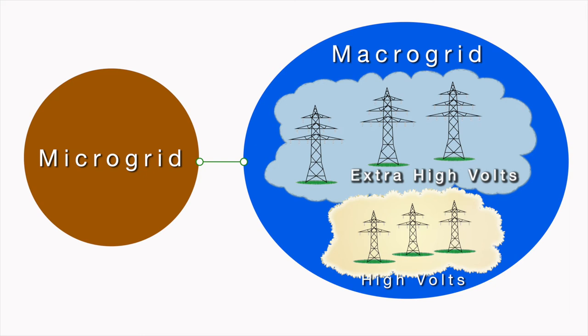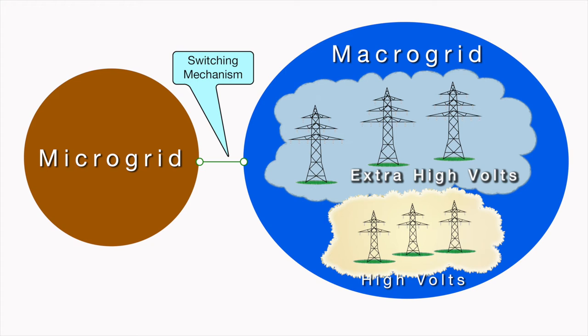Connection of the two grids is via a switching mechanism at the point of common coupling, enabling the microgrid to be switched from island mode to grid-connected mode. Having the ability to connect to the macrogrid addresses issues such as capacity and power quality, whereas switching to island mode can isolate connected loads from voltage and frequency issues occurring on the macrogrid.